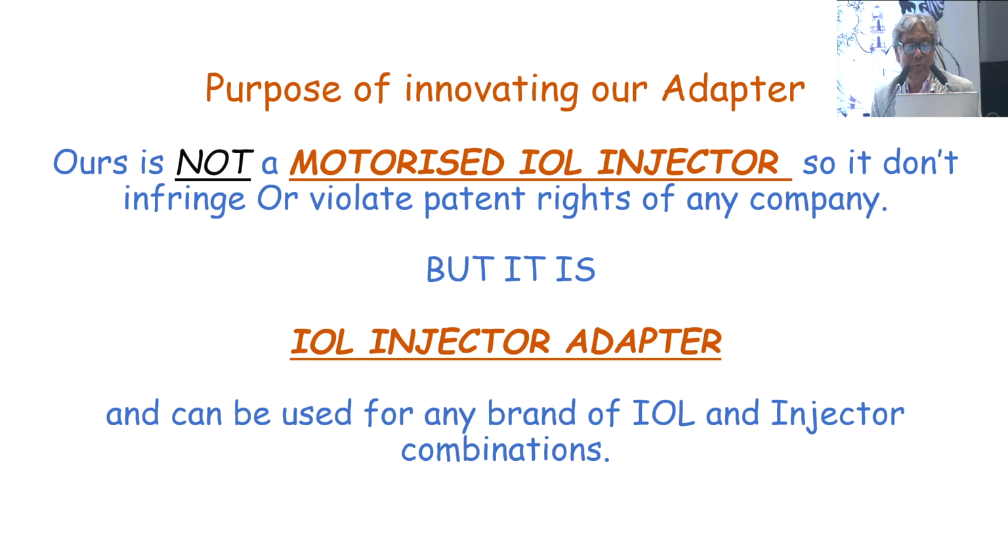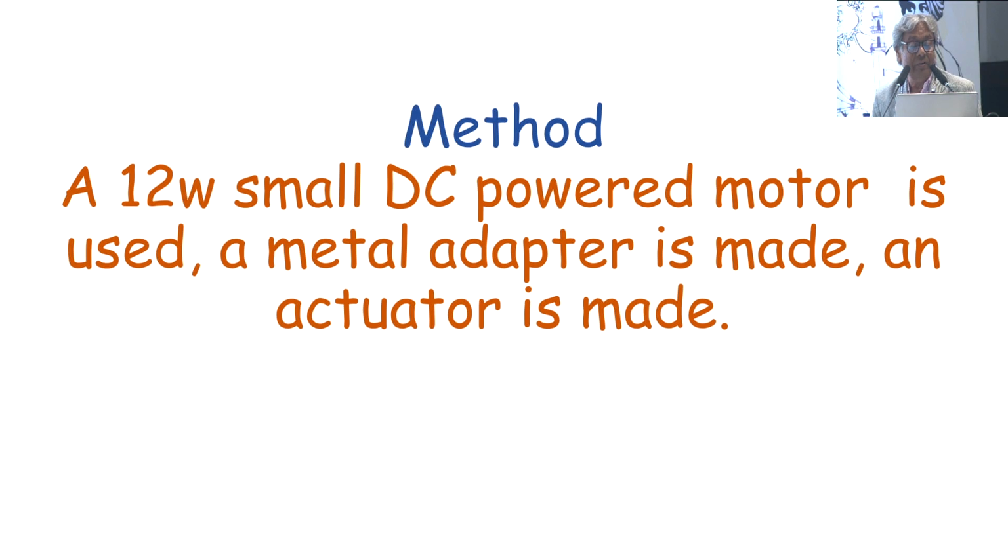The purpose of my innovation of an adapter: it is not a motorized IOL injector, so it doesn't infringe any company's rights, but it is an IOL injector adapter, so it can be used for any brand of IOL, any injector combinations. Method: we have used a 12-watt small DC powered motor, and a metal adapter and actuator are made.